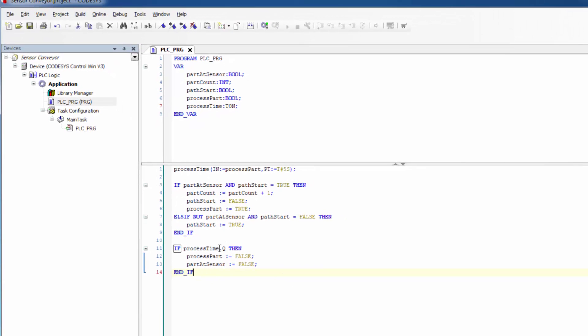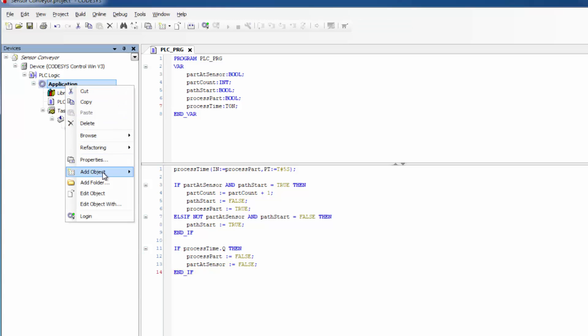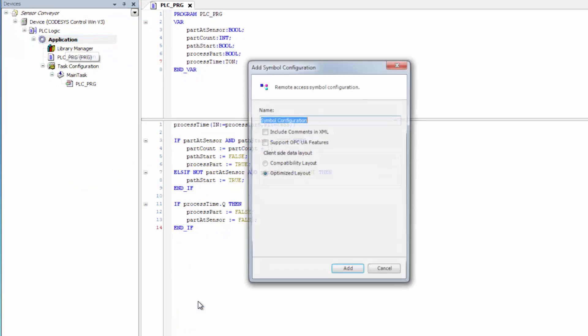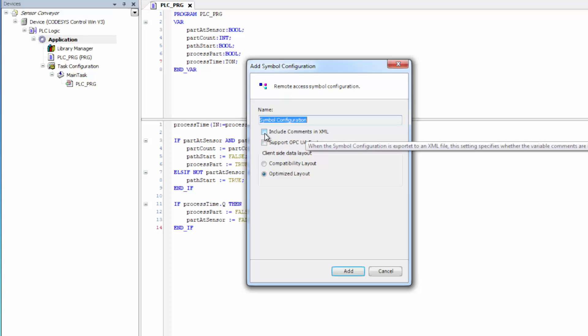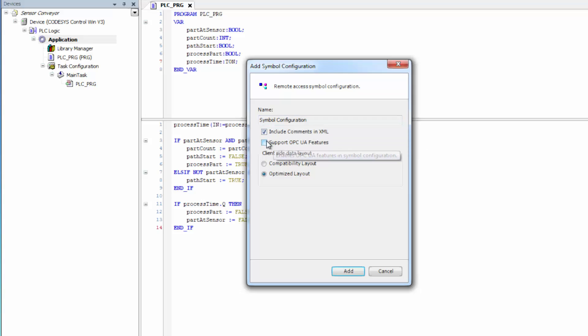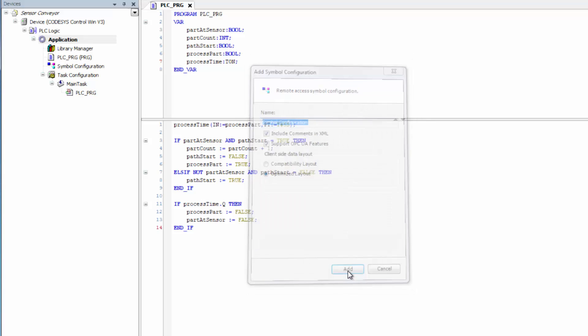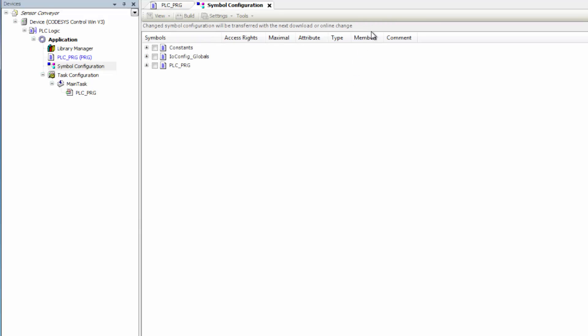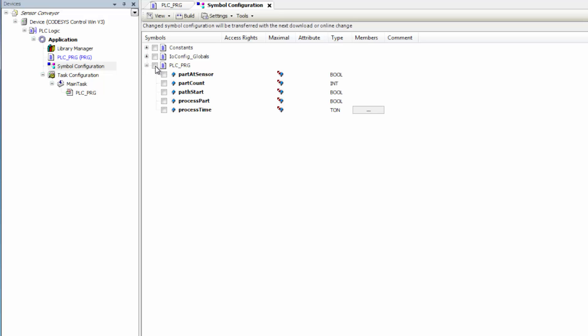To make things compatible with OPC UA, let's add a symbol configuration for these variables. In the application, I'll right-click, then click Add Object, and we're going to add a symbol configuration. We'll include the comments in XML and check the box to support OPC UA features. I'll click Add, then do a build, and choose which variables in my PLC program to include. I'll select the checkbox to select all of them.